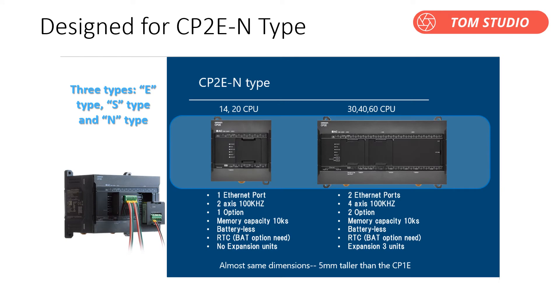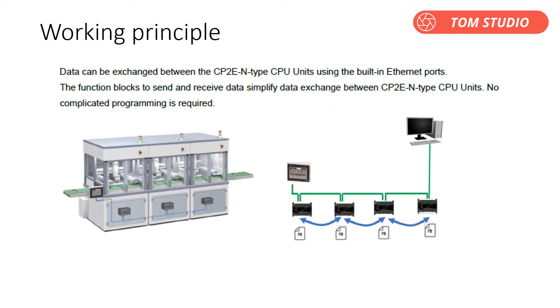Please be aware that the Send and Receive function blocks are only designed for CP2E N-type CPUs. E-type and S-type do not have an Ethernet port, so it is impossible to use these function blocks. The function blocks are designed for data exchange on CP2E N-type CPU units.